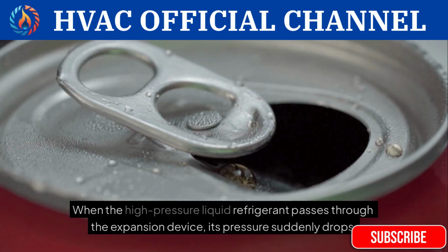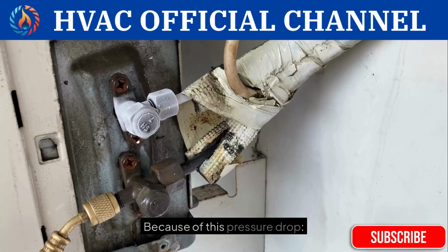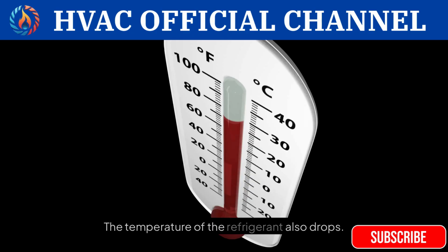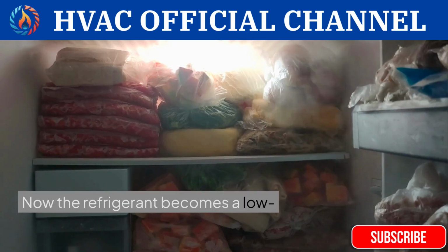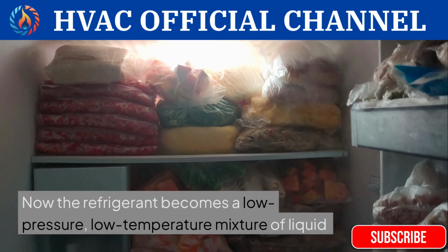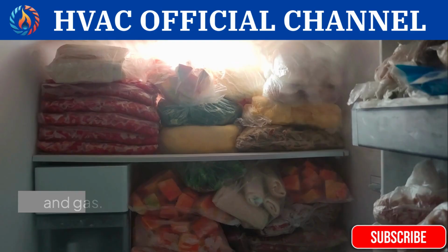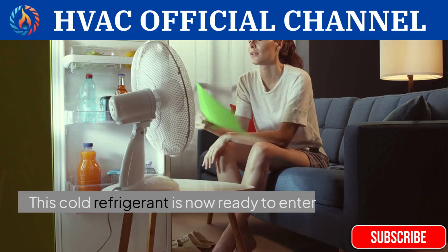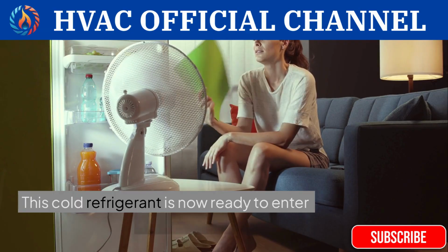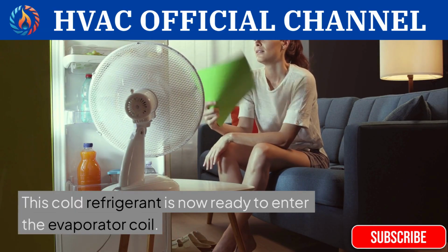When the high-pressure liquid refrigerant passes through the expansion device, its pressure suddenly drops. Because of this pressure drop, the temperature of the refrigerant also drops. Now the refrigerant becomes a low-pressure, low-temperature mixture of liquid and gas. This cold refrigerant is now ready to enter the evaporator coil.